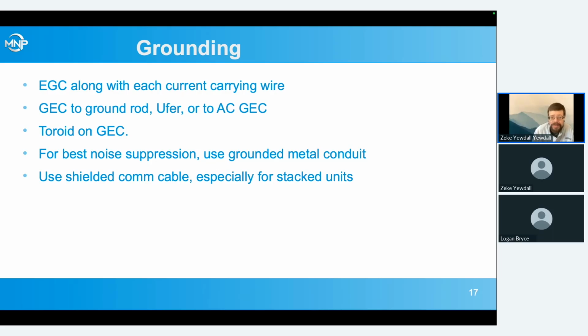So best practice for that is to use shielded comm cable, shielded 4-conductor 18 gauge cable. It's pretty standard security cable, 18 or 22 gauge, and use crimped ferrules on the end of it. It's like $25 for a ferrule crimping tool and a whole package of ferrule ends for that. And you can make high quality comm cables instead of just using whatever random phone cable or thermostat wire you have around to hook up your stacked units, and you'll have a lot fewer errors with the stacked units.